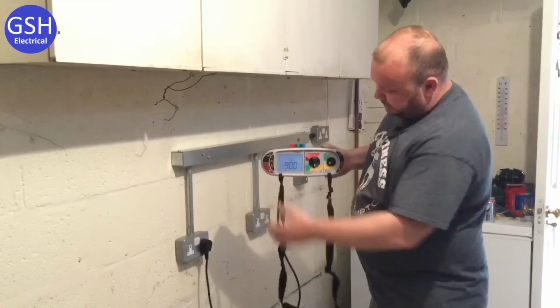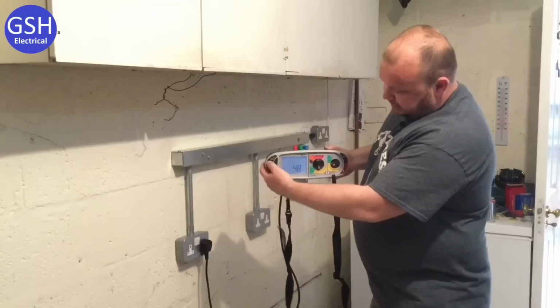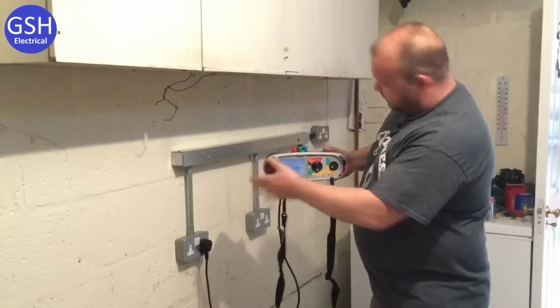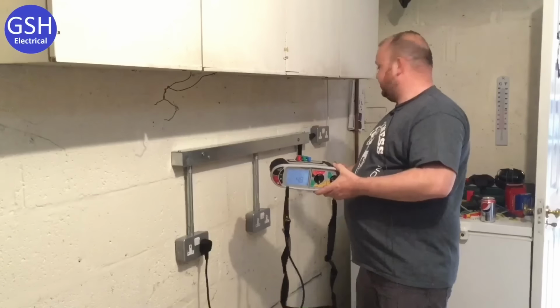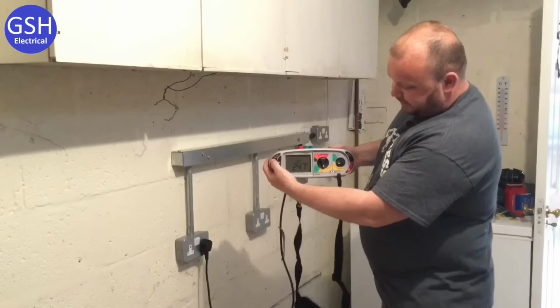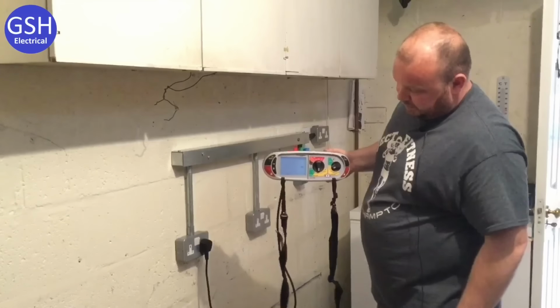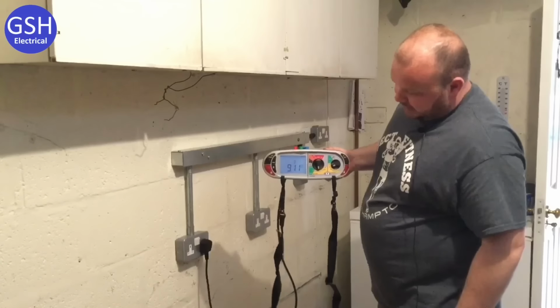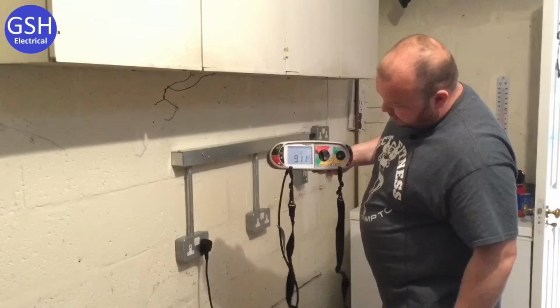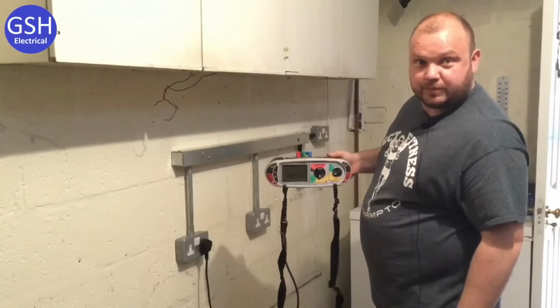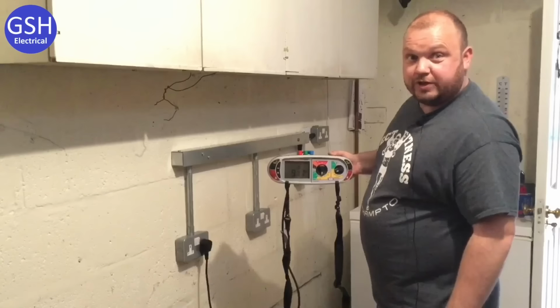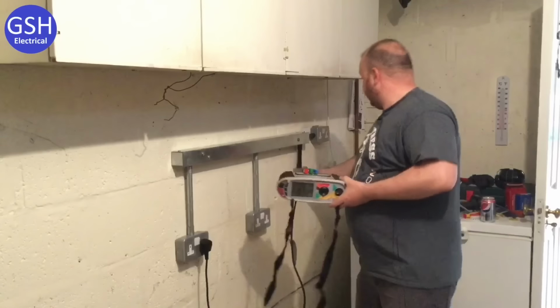Then we're going to change the degree. And reset the RCD, yeah? And we're going to check. You're going to reset the RCD? Sorry, reset the RCD. Okay, excellent. Check again. And that's at 180? 180, yeah. And you've got? 9.11. Of the two readings, which one would you record? Record the highest reading. Okay, thank you. Next. Okay, reset the RCD.